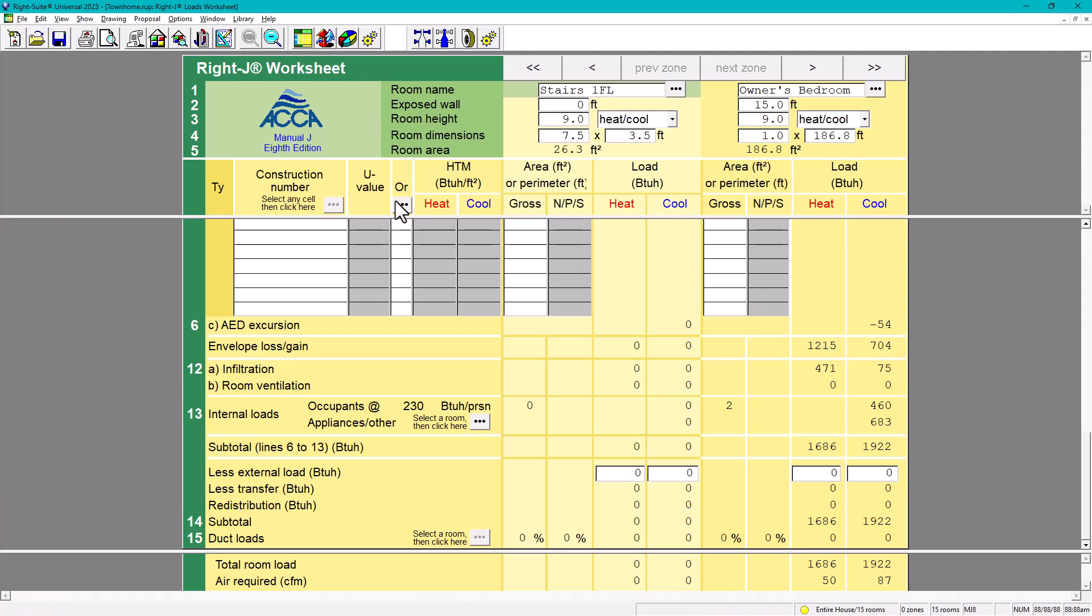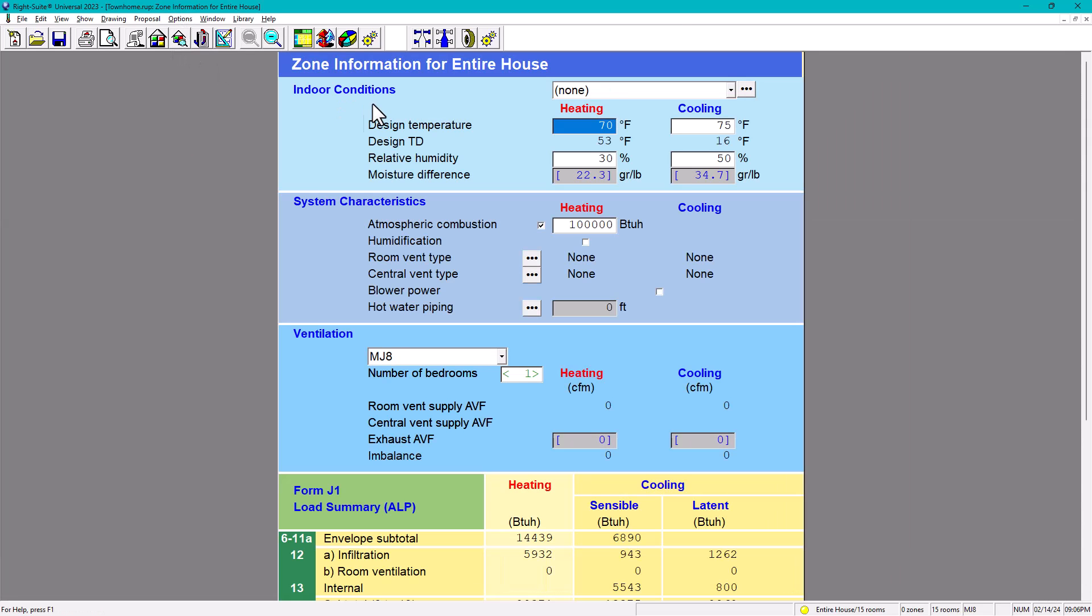After you check your worksheet and you already input your internal loads and everything is good, we're going to go here to the zone information. Under this zone information, you have very important input, but you have a lot of data that you have to input. In here, indoor conditions. What we have is for heating and cooling. For heating, it's usually 70 degrees and 30% relative humidity, and this just populates. For cooling, it's 75 degrees. In other words, the indoor conditions are most of the time based on ASHRAE - 70 for heating, 75 for cooling and 50% relative humidity.